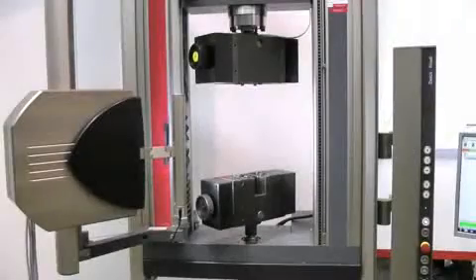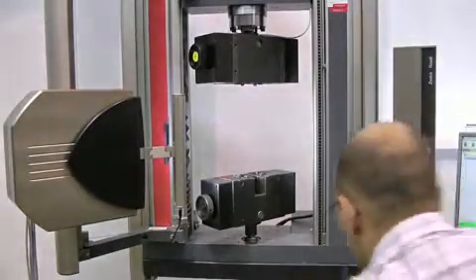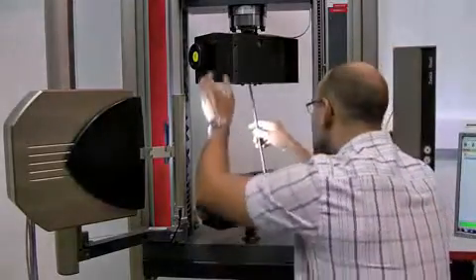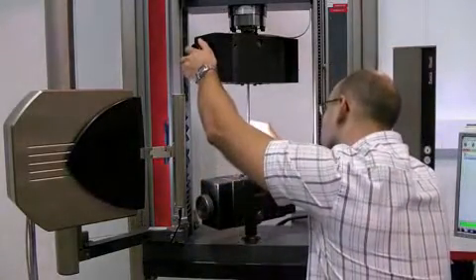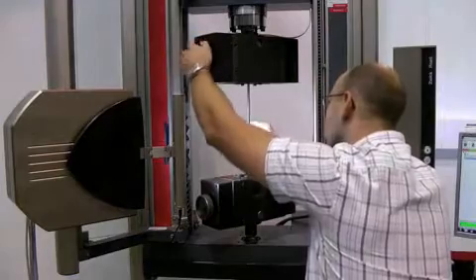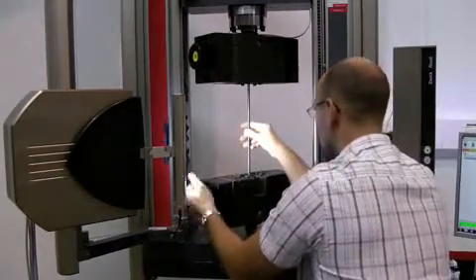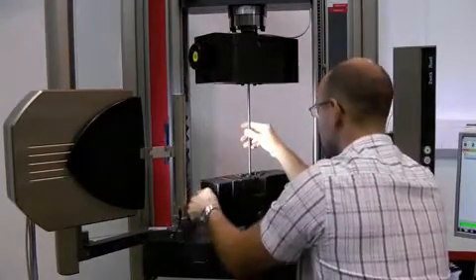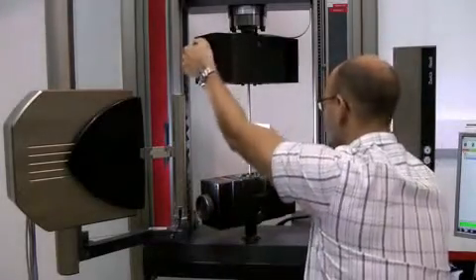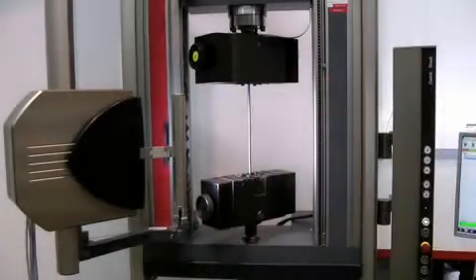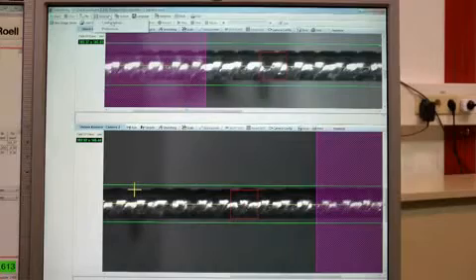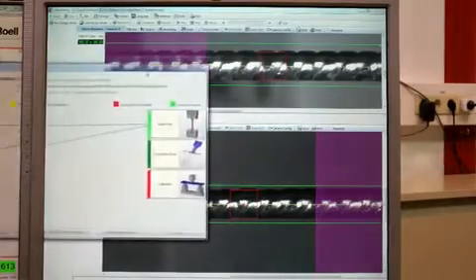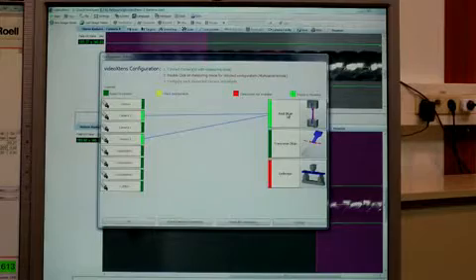A second function of the VideoXtens is the strain distribution function. The strain distribution function allows spreading different markers all over the free length of the rebar steel. Therefore the software is able to center around the necking point at the end of the test.